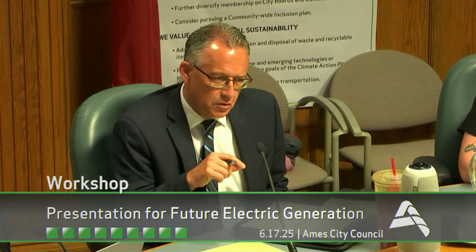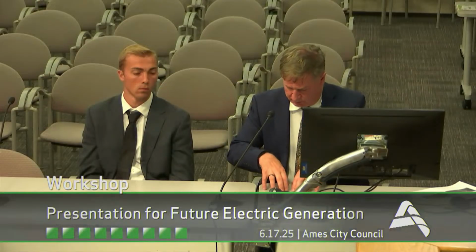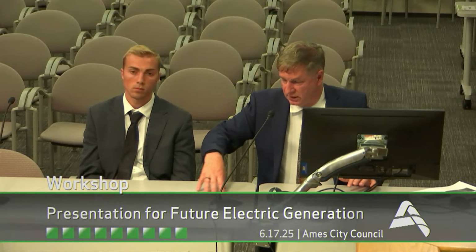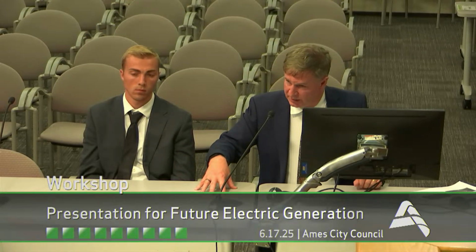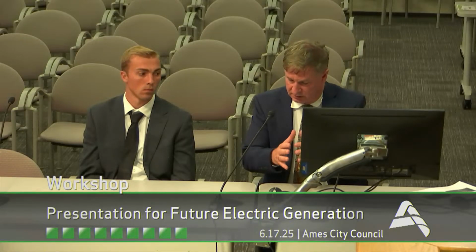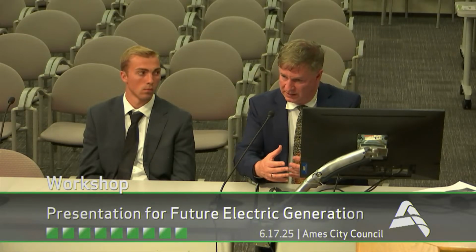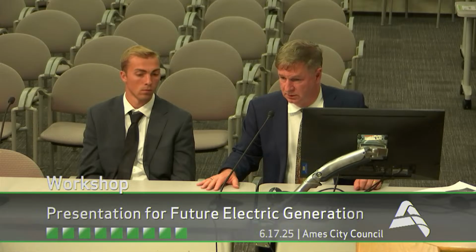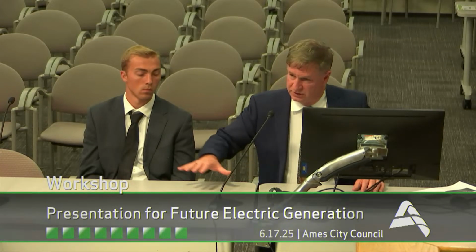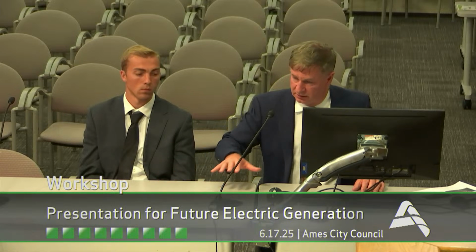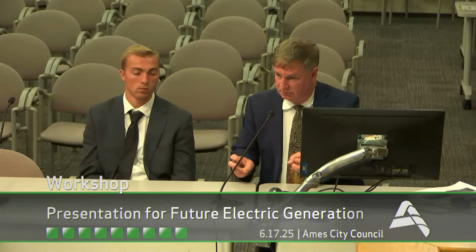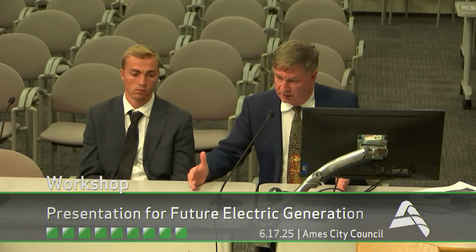Possibly, but let me kind of give you the comparison. So we produce electricity to sell electricity. Iowa State's generation resources are there to make steam for heating and cooling the campus. That's how they size their equipment. Any waste heat that comes off that, they throw into a generator and make electricity with it. So their energy is a secondary process to their heating and cooling, and they have enough capacity, like we were talking about before, to meet their electric needs.